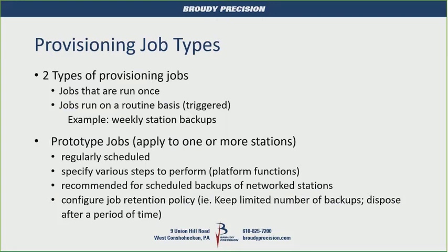There are two different types of provisioning jobs. One is that you run one time. The other would be you run on a routine basis. You would set up like a trigger schedule to do, say, weekly backups of stations. It might be like Saturdays at 2 a.m. or something like that. And then they get saved to your user home. And we'll go through that in Workbench to show exactly where that is.